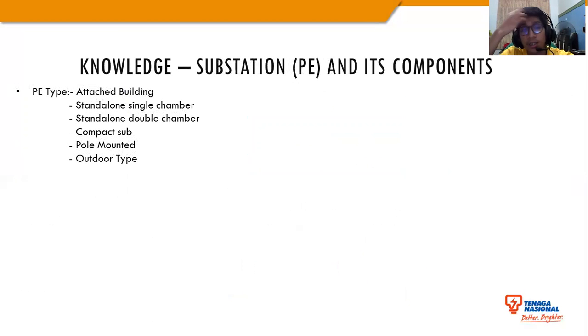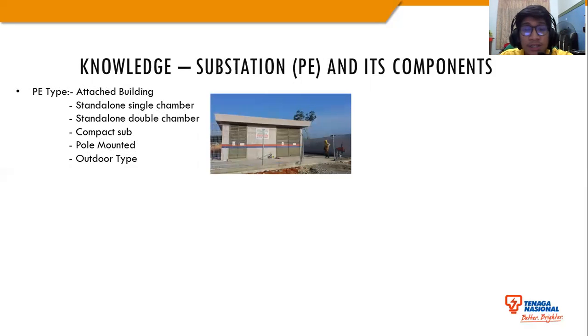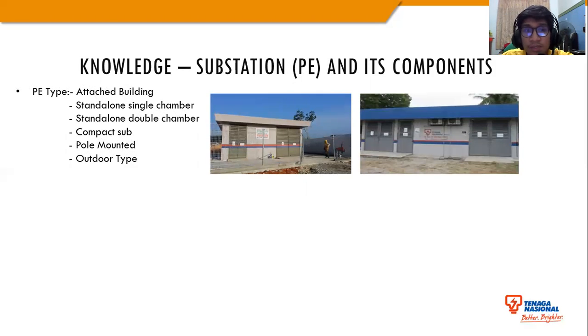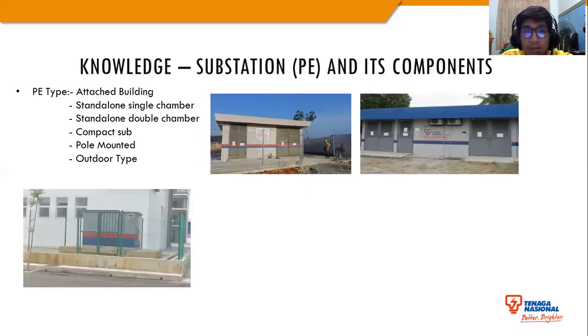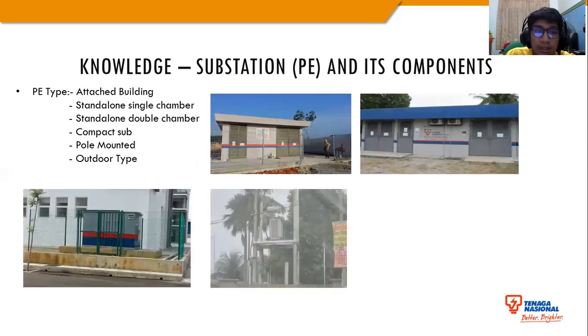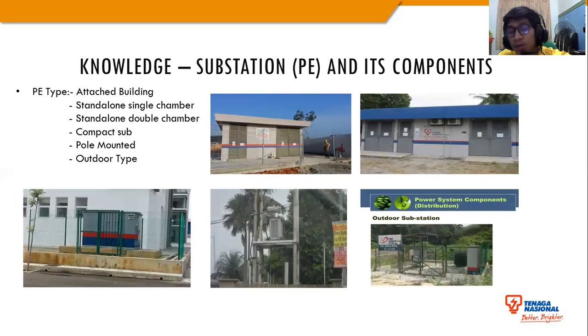So I also learned about the substation and its components. The first one is attached building, where the substation is attached to a building like a factory, maybe at kedai-kedai. The second one is standalone single chamber, where the transformer and the switch gear are put in the same room. Then the double chamber, where transformer and switch gear are put in different rooms. Then the compact sub, where we put everything together, including the LV board. Then pole mounted, where the transformer is put on top of the pole, and that is the outdoor type.